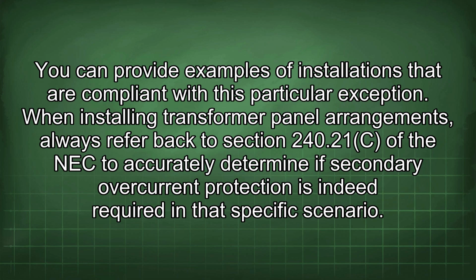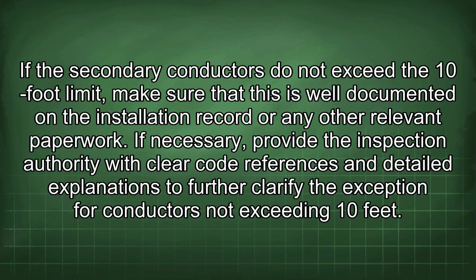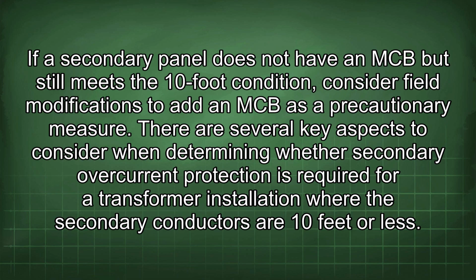When installing transformer panel arrangements, always refer back to section 240.21(c) of the NEC to accurately determine if secondary overcurrent protection is indeed required in your specific scenario. If the secondary conductors do not exceed the 10-foot limit, make sure that this is well documented on the installation record or any other relevant paperwork. If necessary, provide the inspection authority with clear code references and detailed explanations to further clarify the exception for conductors not exceeding 10 feet. If a secondary panel does not have an MCB but still meets the 10-foot condition, consider field modifications to add an MCB as a precautionary measure.